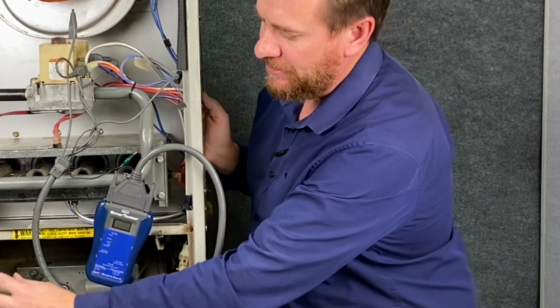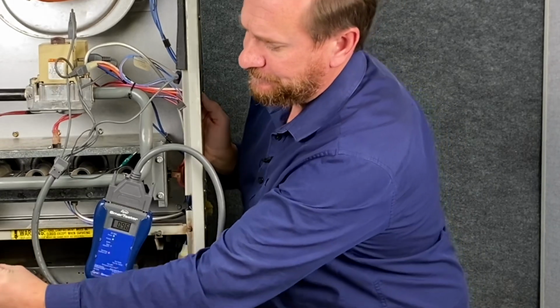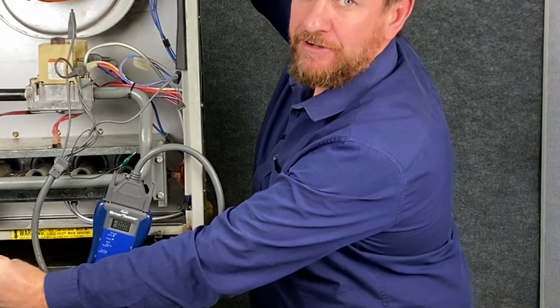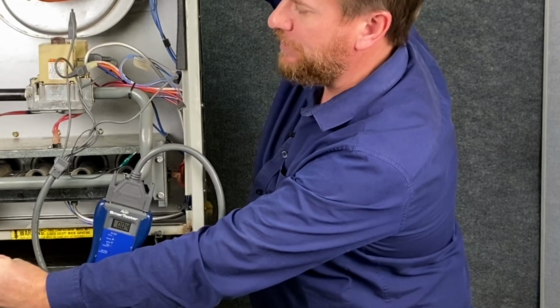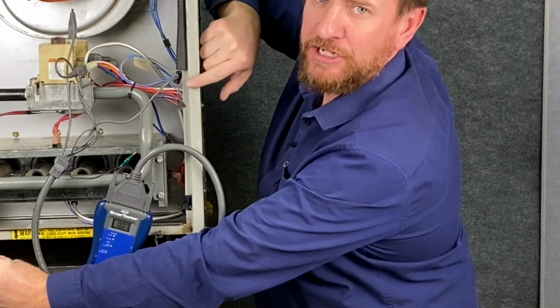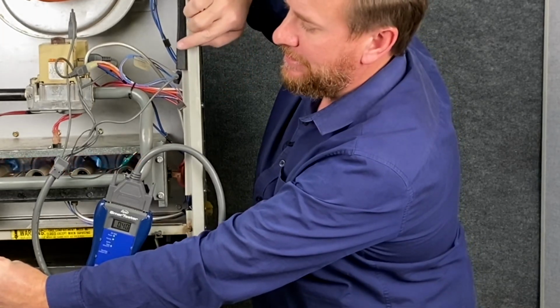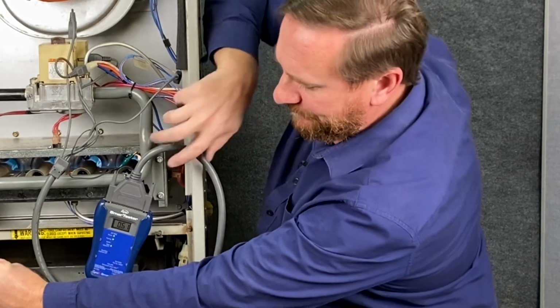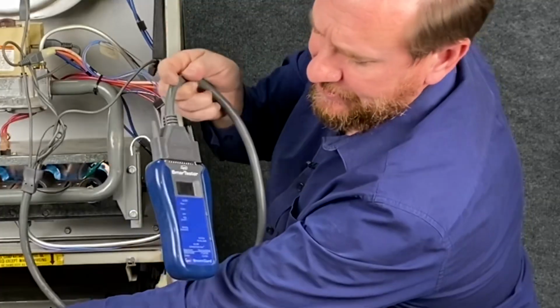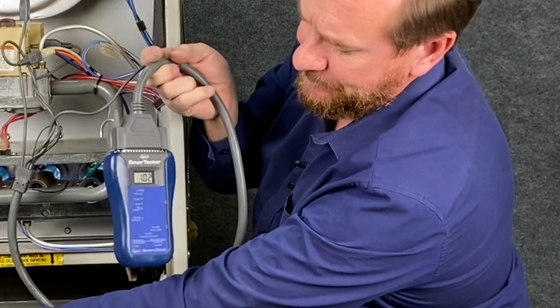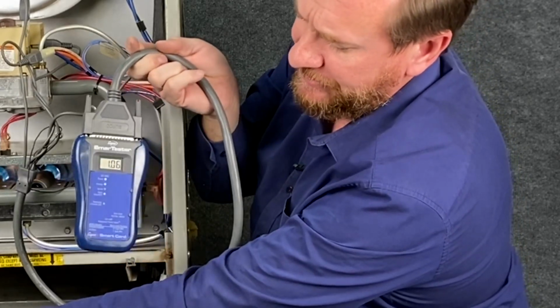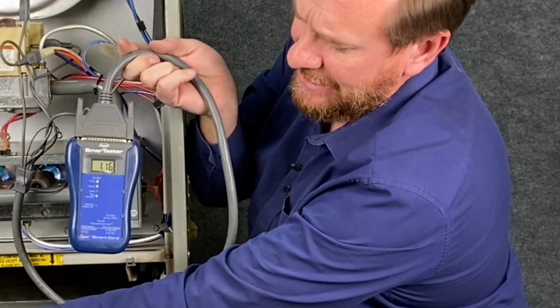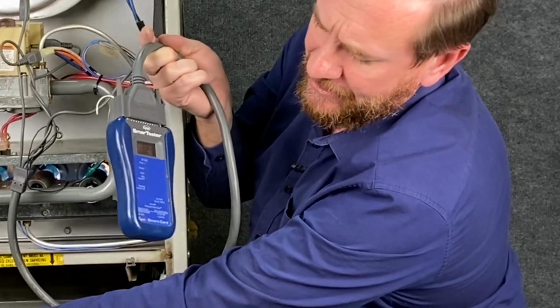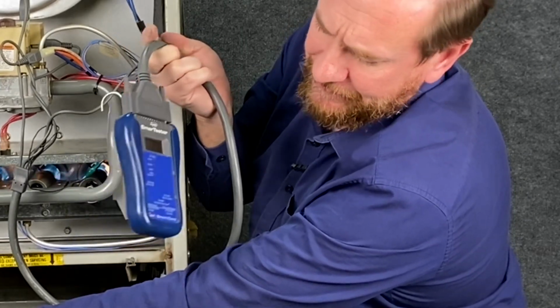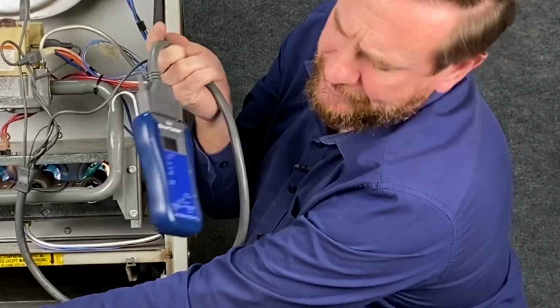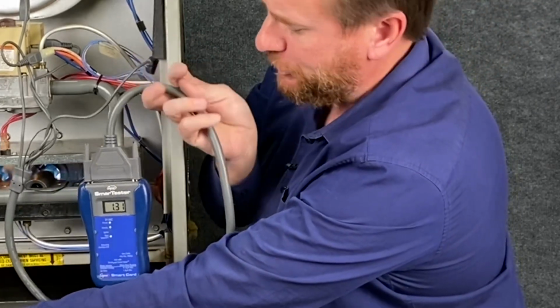of this furnace. So we're going to have our call for heat. Inducer fan first. Pull it back into the pressure switch. We lit our pilot light. We're going to show this shortly at a close-up. Now the pilot light, we lit the main valve. And if we look on our little control right here, it's telling us that our flame sensor is 1.06, 1.08, and we have proper polarity. We have our igniter, we have our main valve, and it's about to turn the blower on. That last little light's going to come on here shortly.